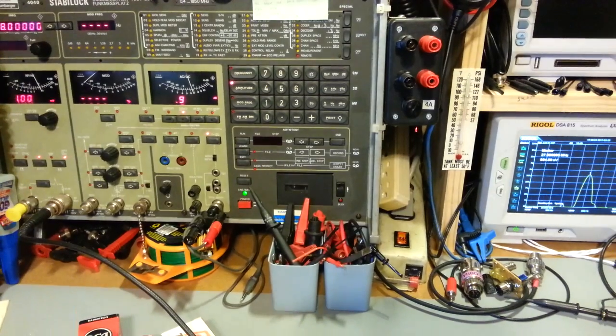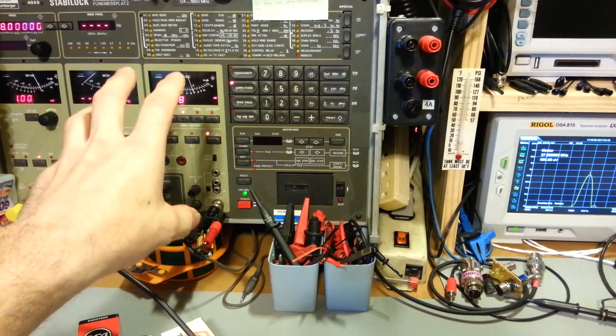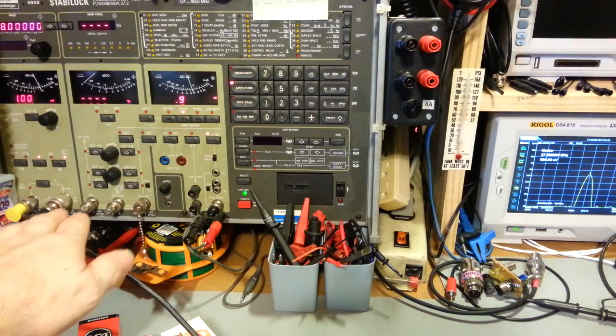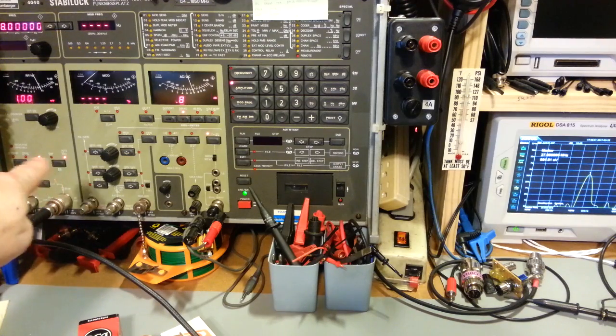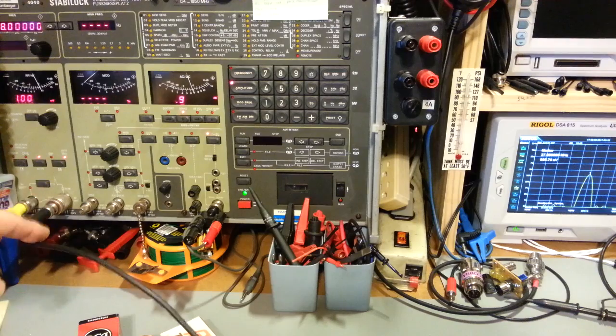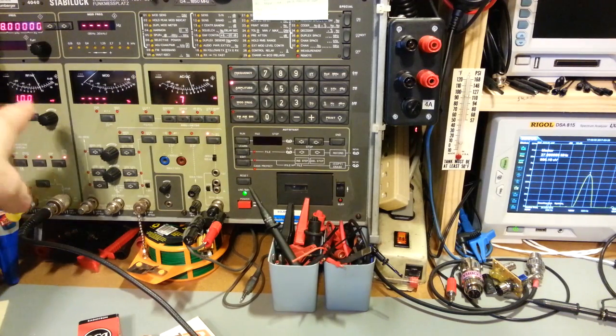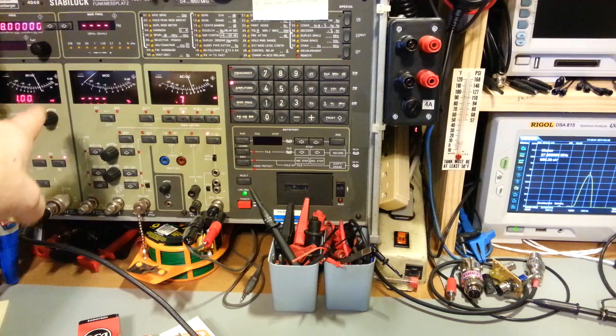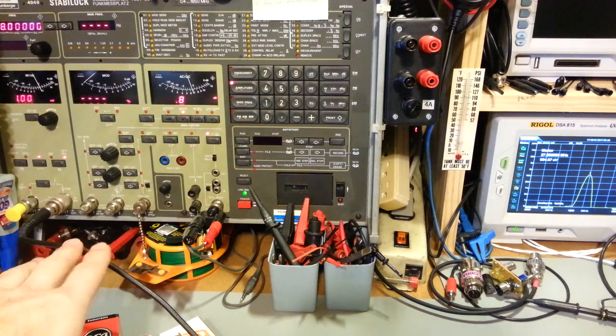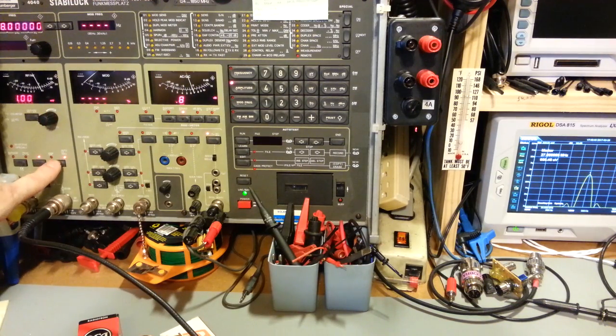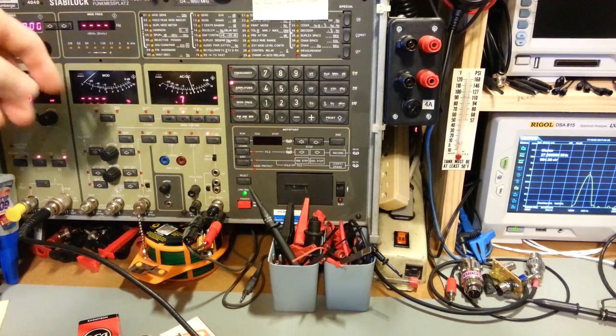So you need to watch that, and also know your test equipment. You need to look it up if it's not printed on there with indications like this one. You may need to look it up in the specifications or literature for your signal generator, to see when it says it's putting out, in this case, 1 millivolt, is that 1 millivolt into 50 ohms, or EMF? Because that's actually 2 millivolts. So just be aware of that.